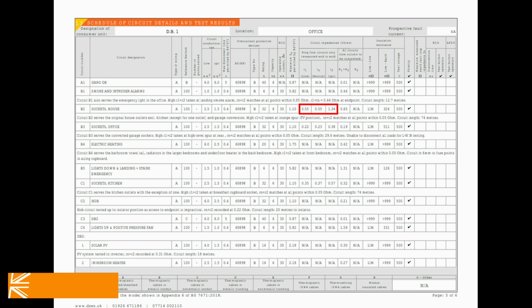Until then, there's not much I can do about it, but I have verified a good earth fault loop path at all accessories on that circuit, and the CPC won't be carrying current under normal operation, so it's not a factor with my AFDDs today. But what if that bad number had been on R1 or Rn? If I can't get to where the fault is, I'd have to look at perhaps breaking the circuit down at the fault position, if it can be confidently identified, into 2 lower rated radials in order to be able to remove the problem and apply the AFDD upgrade.